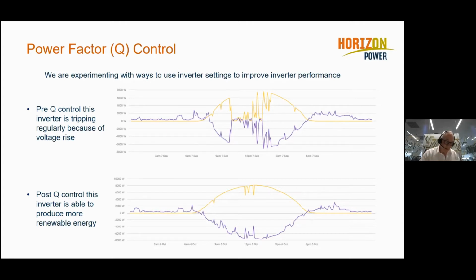When using managed inverters to reduce network voltage, we created this operational advantage which this unmanaged system was able to take advantage of. It didn't pull down the voltage as we had hoped, but it did increase the amount of renewable energy that was exported into the network, which has a corresponding reduction in fossil fuel consumption at the power station. This raises some really interesting questions around the usefulness of Q control to manage network voltages while we still have a significant fleet of older and unmanaged systems connected to our networks.